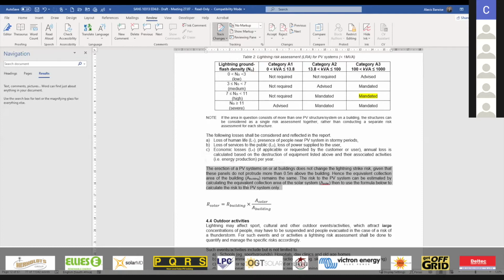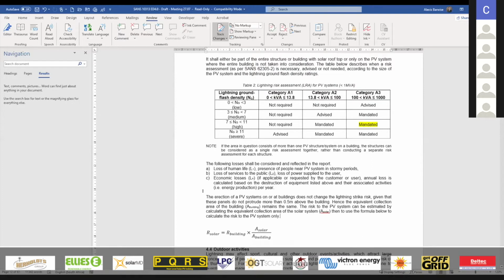That is hogwash. What it does do is bring a different type of risk to the building, which was not there before. Risks like DC arcing, risks like fire starting, risk like loss of economic impact, in the sense that the actual generator is not generating any revenue. But it does not make or attract the lightning. That is not true. We have a very clear statement here to say that if the PV system does not protrude more than 0.5 meters above the building, then the effect of that PV in terms of the frequency of lightning is absolutely zero.